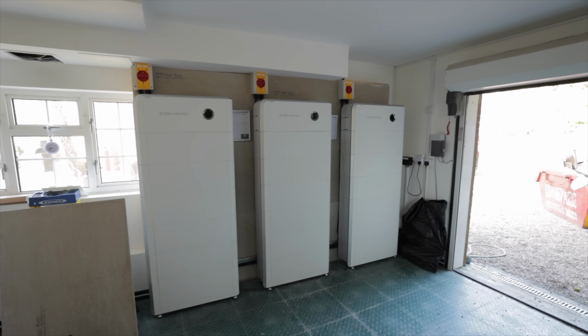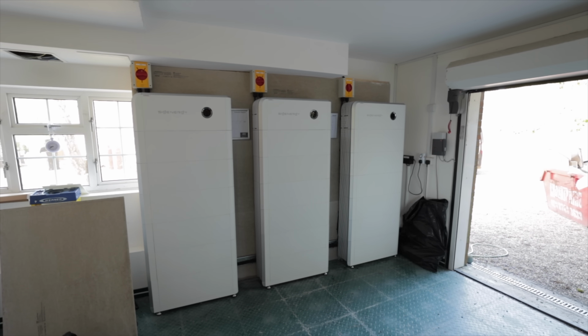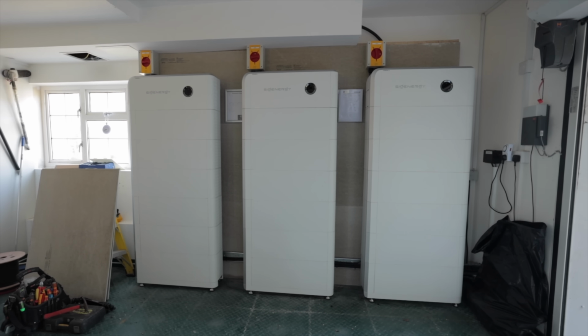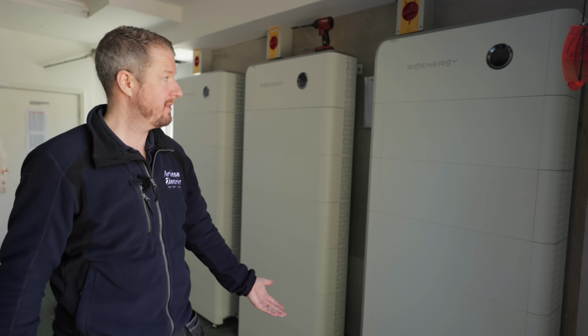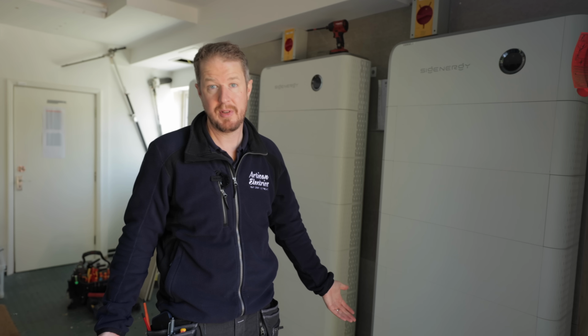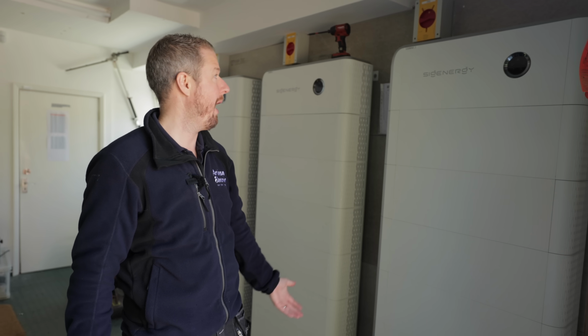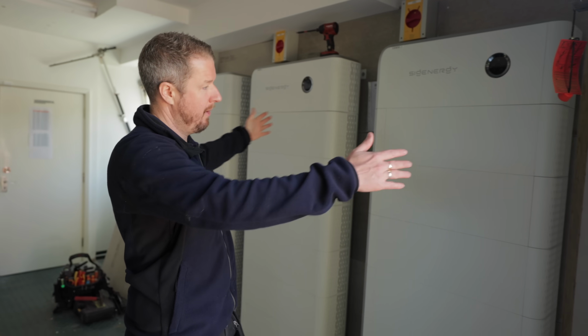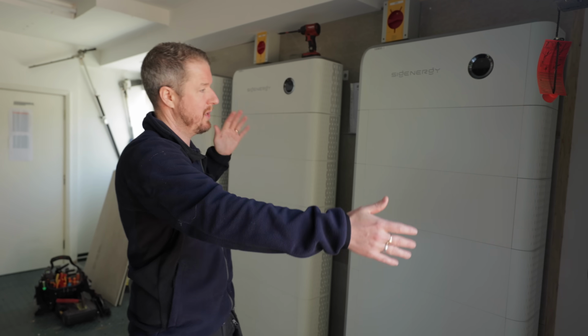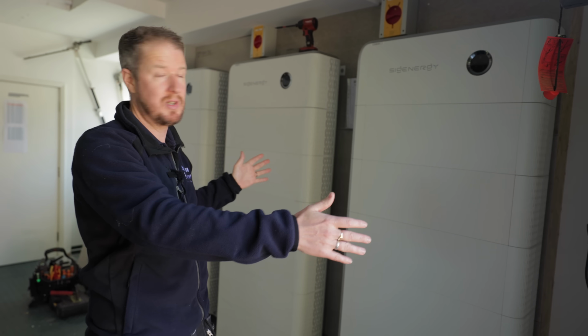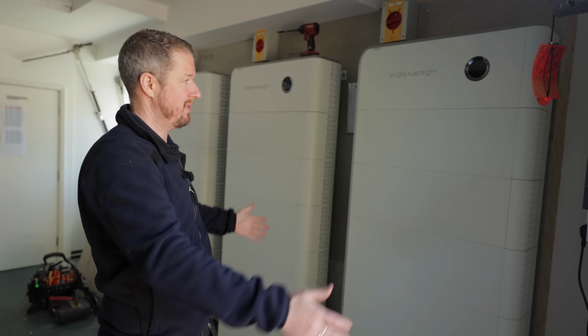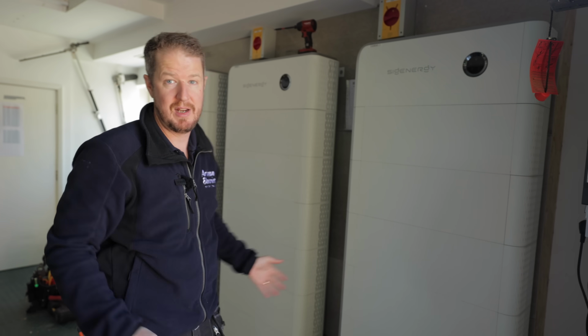It's also about wall space, right? So you need a large amount of wall space to fit batteries on. Now, one stack like this might be sufficient for most householders. That's 48 kilowatt hours, and there's about 2 meter by 1 meter space needed. We do need a bit of clearance between each stack per the manufacturer's instructions, to give ventilation, etc.